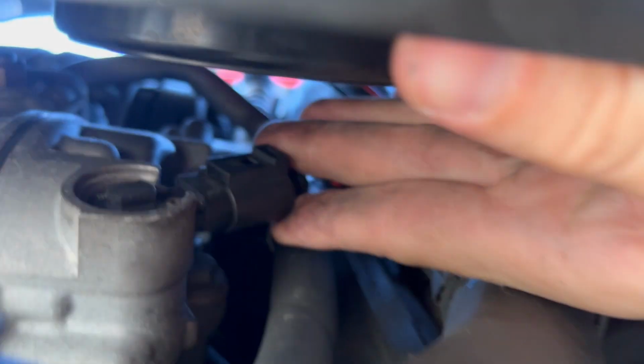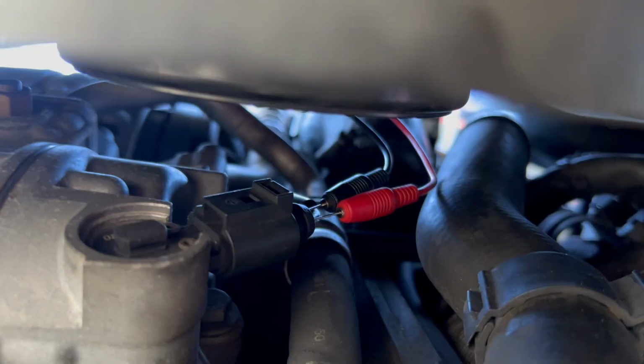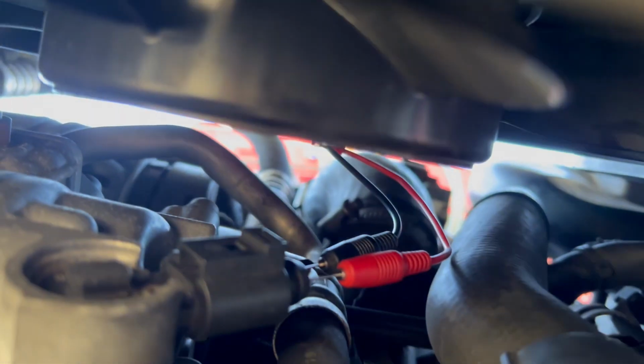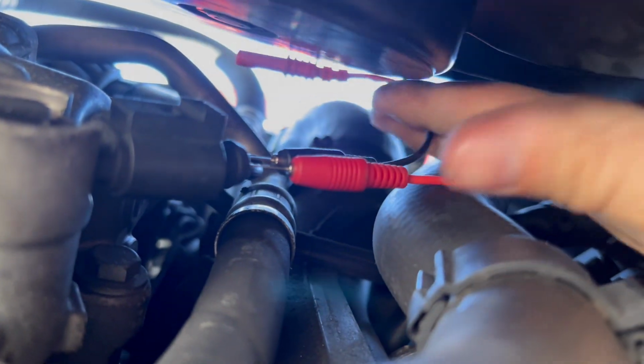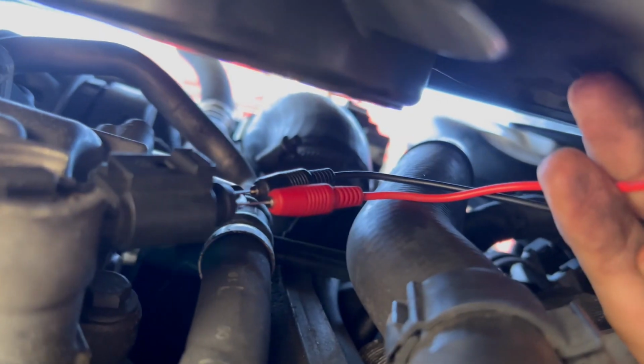There's a reason for that. I absolutely cannot stand puncturing the insulation and then not redoing it, because of moisture contamination, corrosion, and things like that. I don't like causing problems in electrical systems that don't need to be there. So always, always, always back probe.